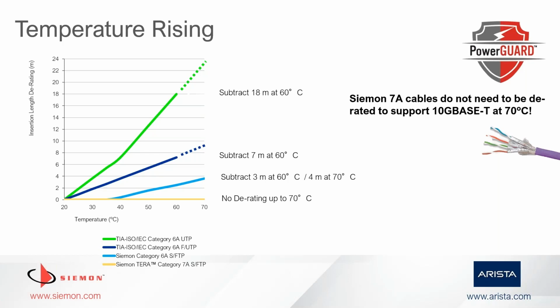If we look first at the length derating due to the temperature rising, you can see that referring to the ISO standard, Cat6a UTP cable at 60 degrees will need to subtract 18 meters from the total amount allowed, typically 90 meters at standard temperature. With a shielded cable, derating will be lower, so only 7 meters will need to be subtracted from the total of 90. While with our Siemon cables, we have even better performance with the same kind of cable.